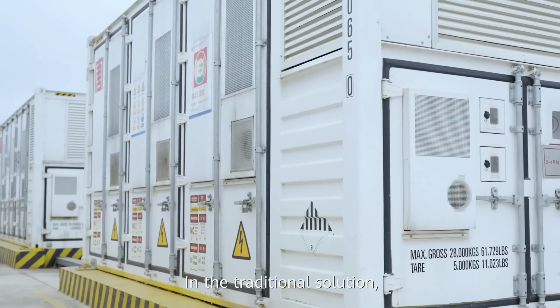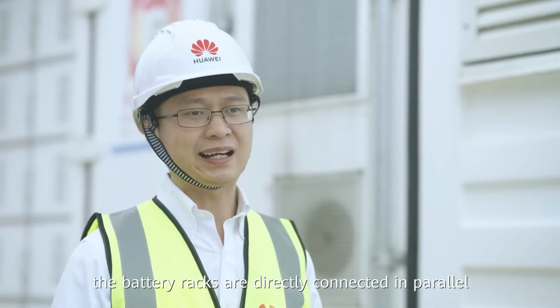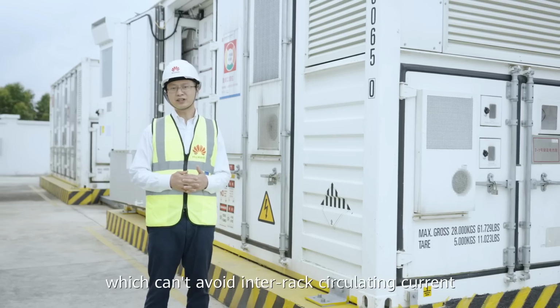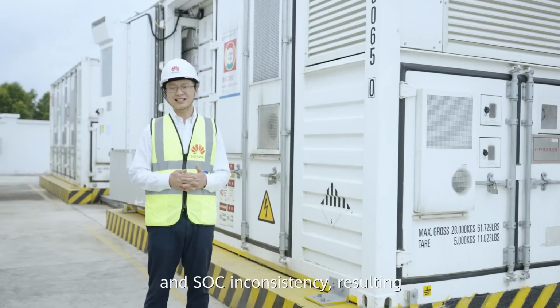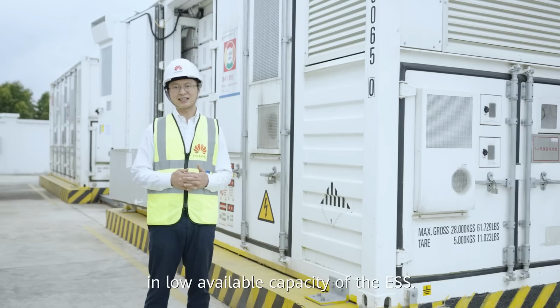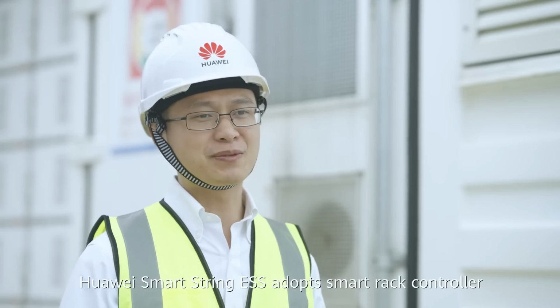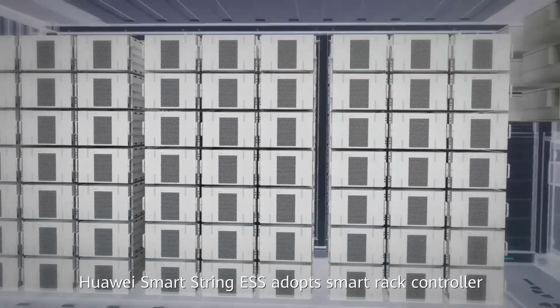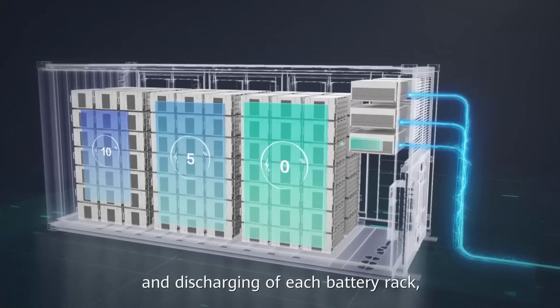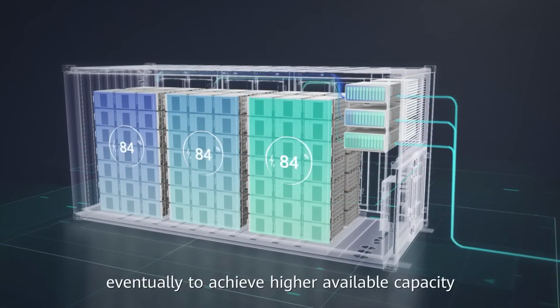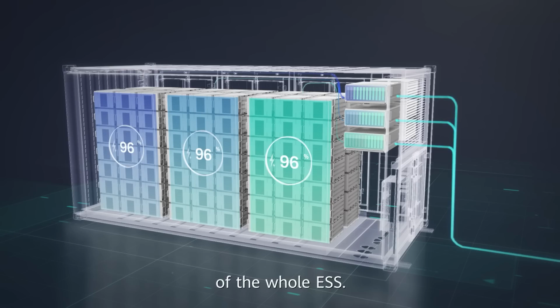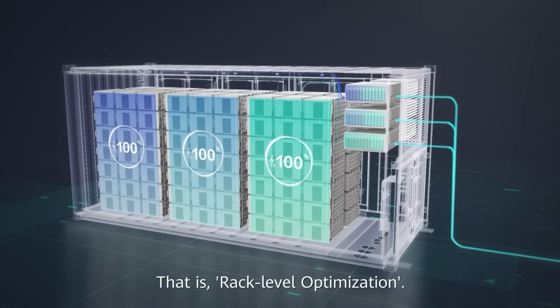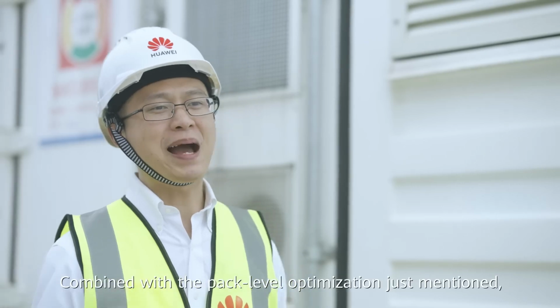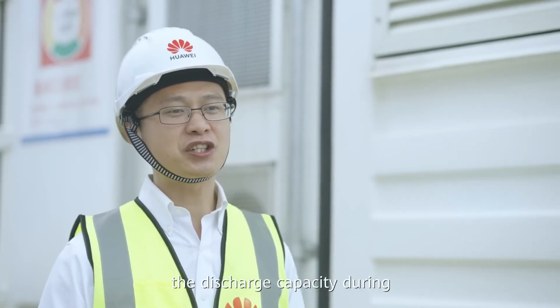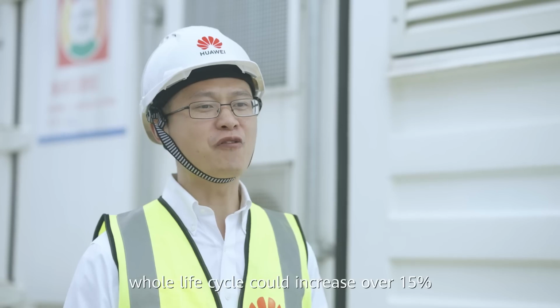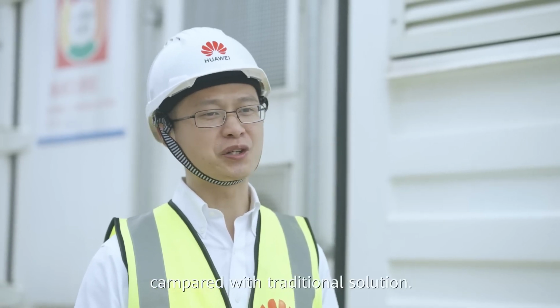In the traditional solution, the battery racks are directly connected in parallel, which cannot avoid the inter-rack circulating current and SOC inconsistency, resulting in low available capacity of the ESS. HUAWEI Smart String ESS adopts smart rack controller to realize the independent charging and discharging of each battery rack, eventually to achieve higher available capacity of the whole ESS, that is, rack level optimization. Combined with the pack level optimization just mentioned, the discharge capacity during the whole life cycle could increase over 50% compared with traditional solution.